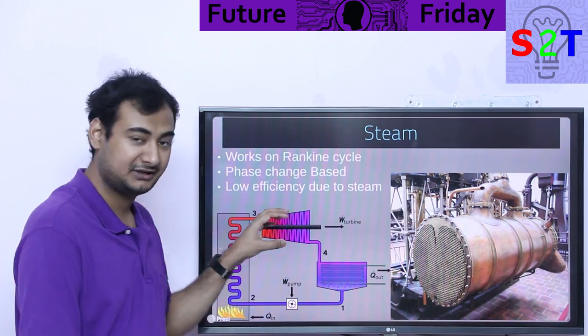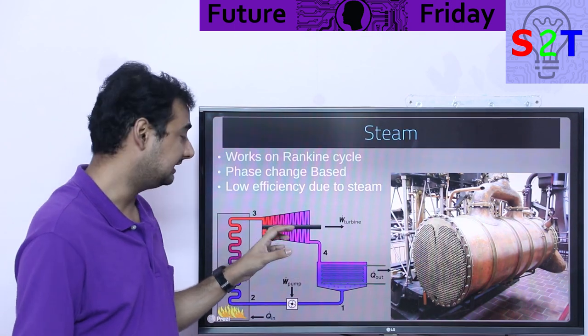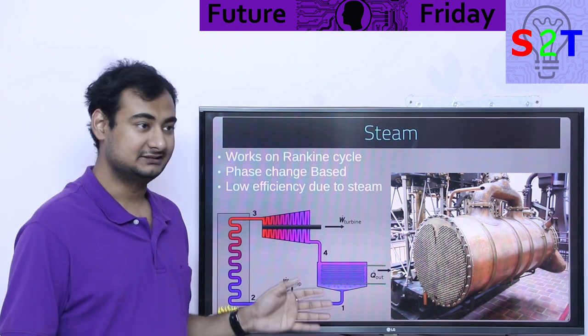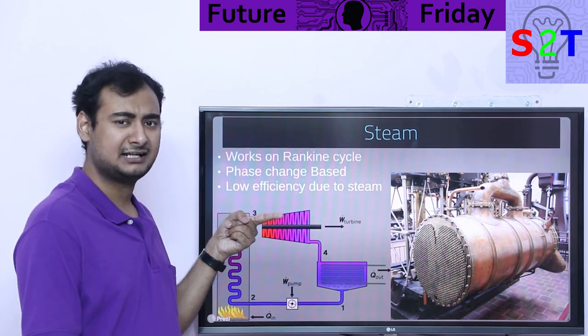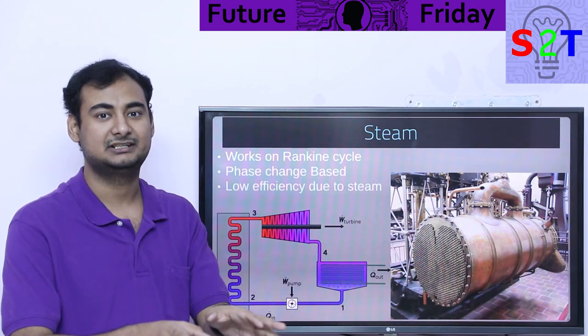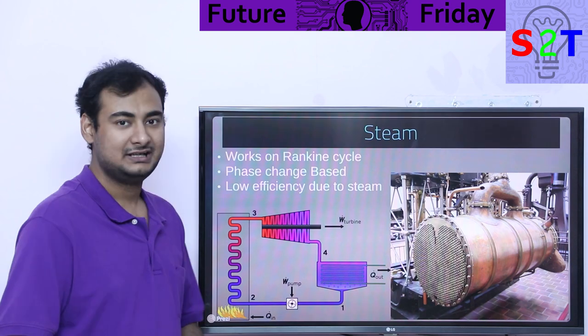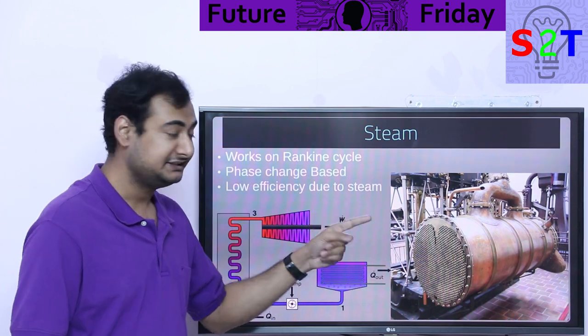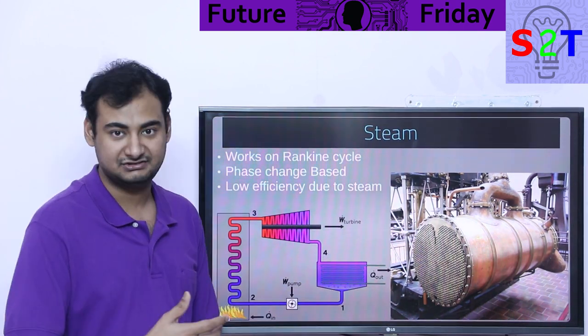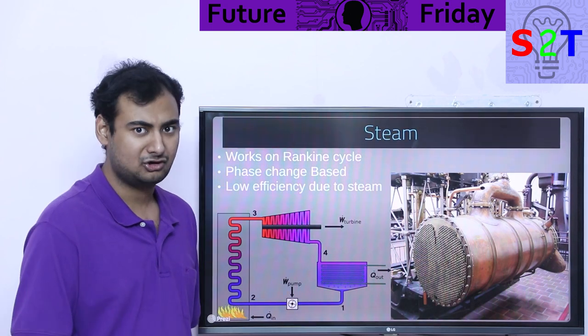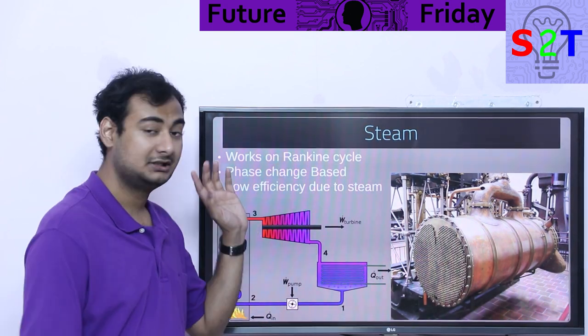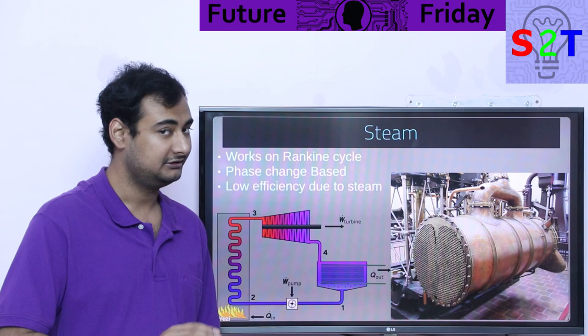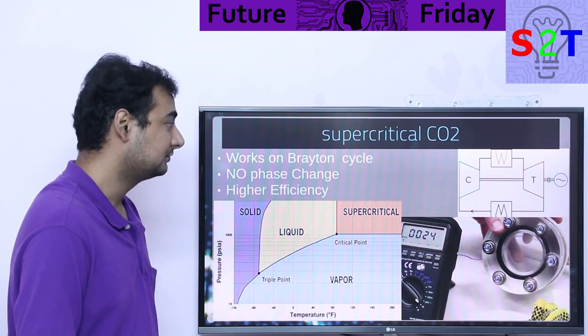Due to this inherent nature, you are losing energy. The ideal turbine would send in ludicrously high pressure steam and the exhaust would be raw liquid, but we don't have that. Most of the output is still steam, so you still need a condenser unit that inherently wastes energy. This is the thermodynamic limit that the Rankine cycle itself locks us into — we cannot push beyond a certain point, so we look into supercritical systems.